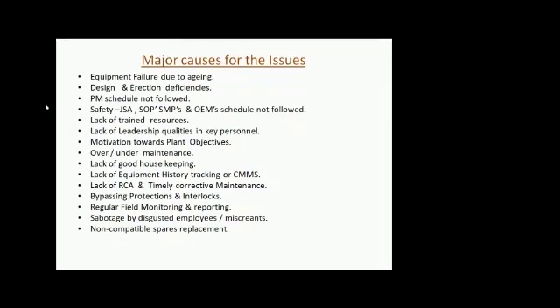Another part is bypassing protections and interlocks. This is a major issue. Most people know that whenever something is tripping or not starting, we need to understand why. Somebody will find out the problem, maybe suction pressure is not okay, or the suction valve is not open, or it's open but its feedback is not coming. These things need to be properly understood.